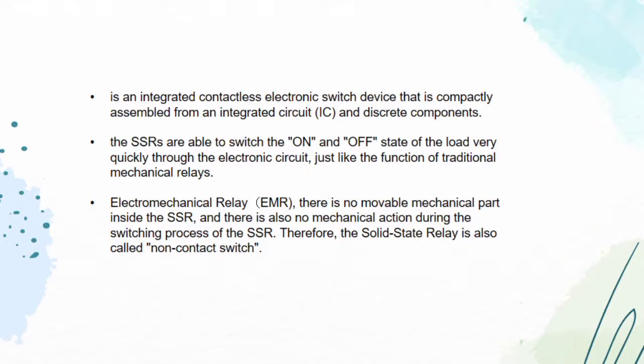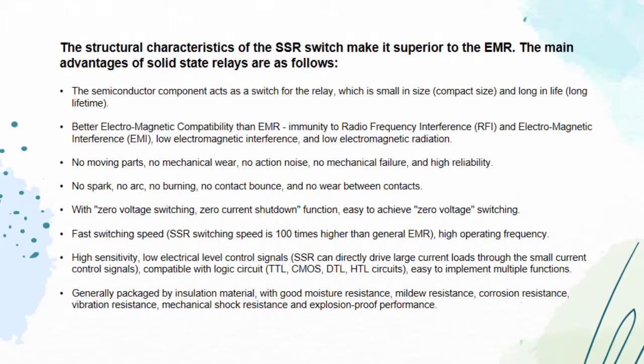Compared with the previous coil-reed contact relay, namely the electromechanical relay or EMR, there is no movable mechanical part inside the SSR, and there is also no mechanical action during the switching process of the SSR. Therefore, the solid-state relay is also called a non-contact switch. So now let's proceed to the next slide.